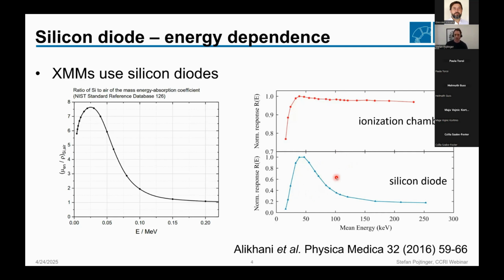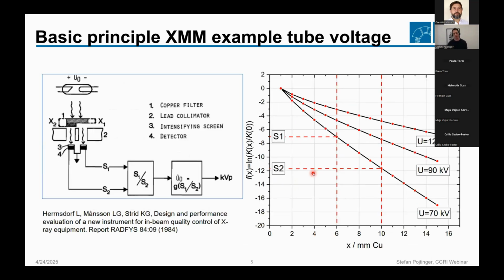What you now might ask yourself is, how can it be that these devices work so well? Because, well, you have this dependence here, but still they are showing the right value if you use the device. And the reason why it works is that all of the devices have implemented a more or less complicated algorithm to compensate for that energy dependence. And this slide is to give you a rough idea how it works.